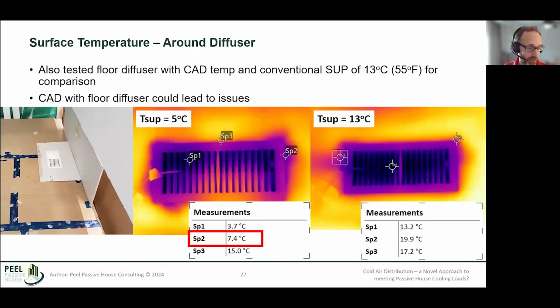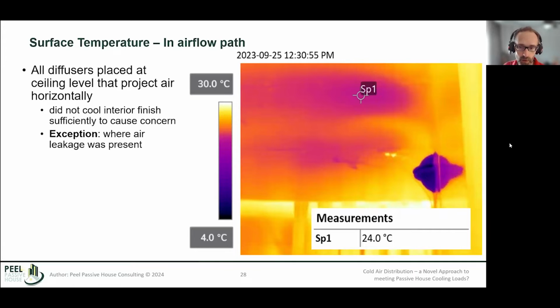We even did a reference of floor. This is very typical, at least in Canada, of having floor-mounted diffusers, air pushing out from above. And certainly at the cold air temperature, that was problematic. So generally not recommended anyway. But yeah, this certainly wouldn't work with cold air distribution. So essentially, what we found is, if you're projecting it using the Coanda effect, it works well.